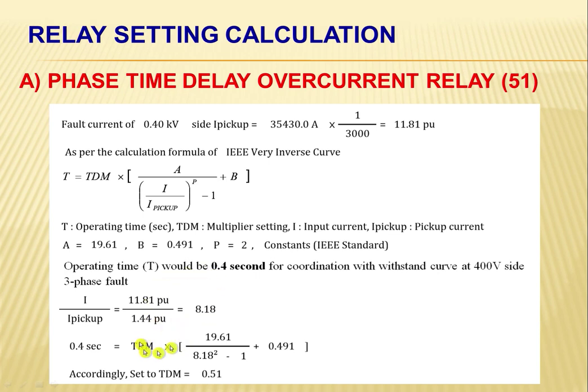Okay, so to solve for the multiplier setting, we're going to substitute for the time the 0.4 seconds, right? And for this ratio, we have 8.18, and the P we have 2. So that's why we have 8.18 squared. Okay, and let's substitute the values of A and B. A here is 19.61 and B here is 0.491.